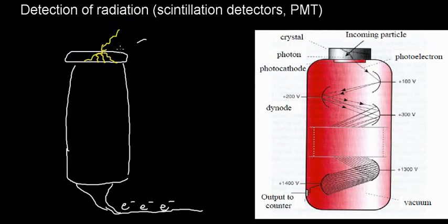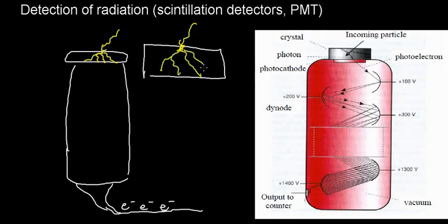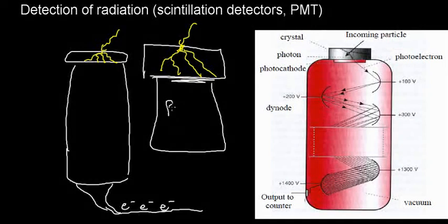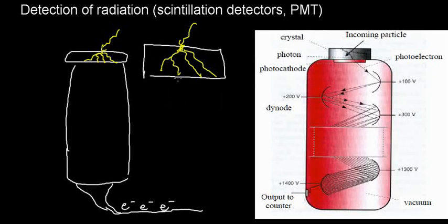And if I'm going to zoom here just for a second, I have my photon coming in, and then the property of this crystal is that it takes this photon and it just turns it into a flash that is traveling across. When it gets to the end, we have this tube. It's called the photomultiplier tube. It's this guy here. When it gets to this tube, these little incident light flashes are going to be turned into electrons.